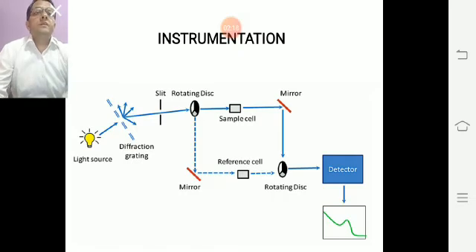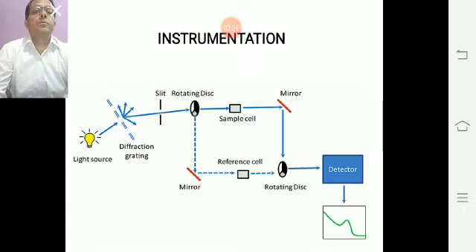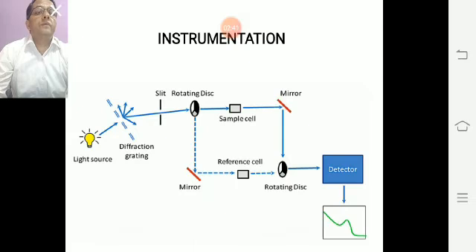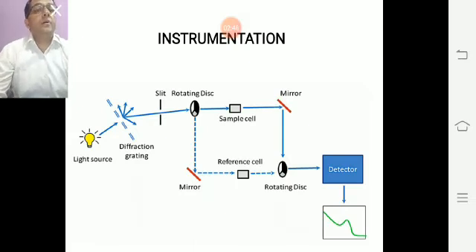Here is the instrumentation. We use a light source — different light sources for different purposes — and here is the diffraction grating. We also use a slit for selecting a particular wavelength, and here is the sample cell or reference cell, and here is the detector, which detects transmitted light and plots it in a plotter.